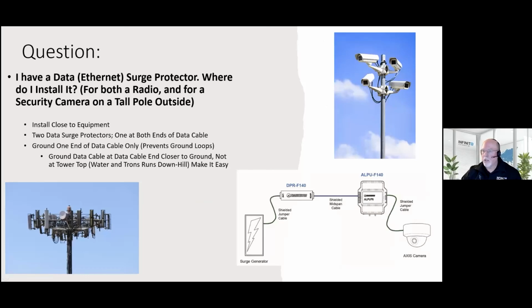Okay. So we've got data protection, and we talked about that, camera protection, for example. This is a picture from a test we did with Axis, which is a very expensive security camera company. So that's their camera here. And then we used an outdoor data protector, gigabit power over Ethernet, and one down by the switch simulation. And the results were just great. Again, you've got long data cables going to your tower top, whether it's radios or a camera, you'll want to use a surge arrestor at both ends of that data cable.